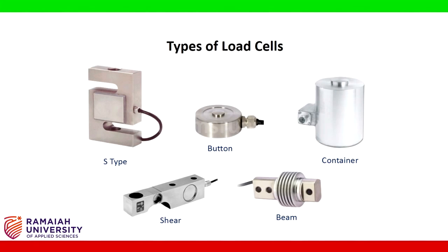Based on the applications needed, different types of load cells are available. Some of those load cells are as follows: S-type, shear type, beam type, container type, and button type. In the laboratory, a beam type load cell will be used to measure the weight or force.